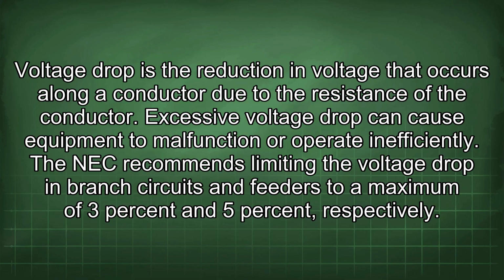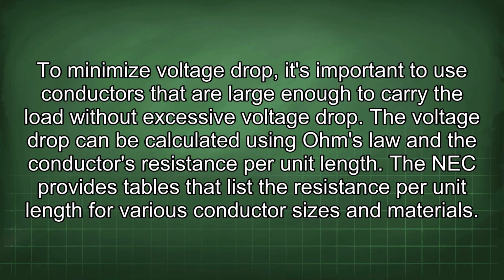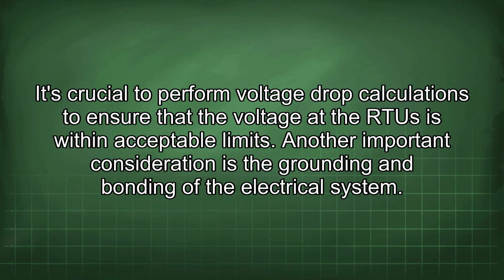Excessive voltage drop can cause equipment to malfunction or operate inefficiently. The NEC recommends limiting the voltage drop in branch circuits and feeders to a maximum of 3% and 5% respectively. To minimize voltage drop, it's important to use conductors that are large enough to carry the load without excessive voltage drop. The voltage drop can be calculated using Ohm's law and the conductor's resistance per unit length. The NEC provides tables that list the resistance per unit length for various conductor sizes and materials. It's crucial to perform voltage drop calculations to ensure that the voltage at the RTU is within acceptable limits.